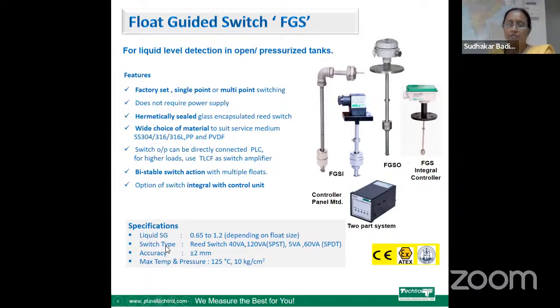The switches are available for liquid specific gravity from 0.65 to 1.2. The switch type is reed switch. They are available as 40 VA, 120 VA in SPST form, or 5 VA or 60 VA in SPDT forms. Accuracy is plus minus 2 mm and suitable for maximum temperature of 125 degrees Celsius and 10 kg per centimeter square.